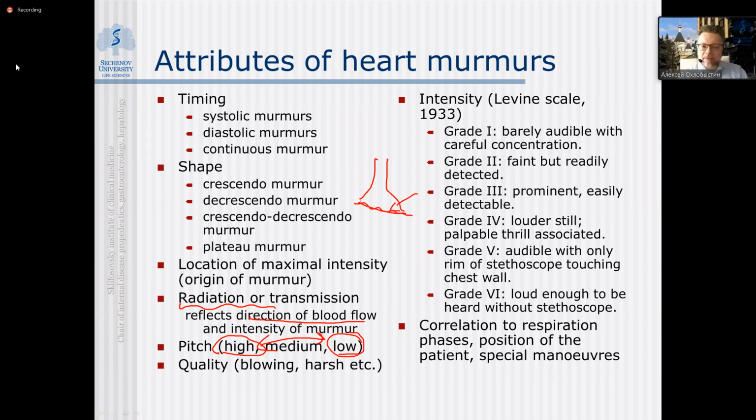The point is that membrane will amplify high frequency murmurs to high extent. Yes, the vibration. So vibration through the diaphragm membrane will go. That is a tube, that's a stethoscope that actually did not change significantly from the time it was wooden. It will conduct more or less evenly all murmurs. But membrane that was added will act as an amplifier, but amplifier is quite selective. It will amplify in high degree, high pitch sound, and there'll be almost no amplification for low pitch sound.